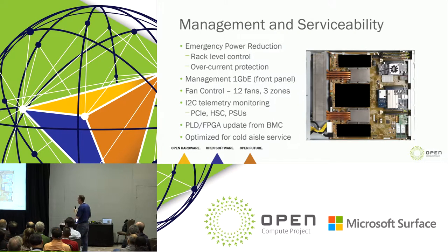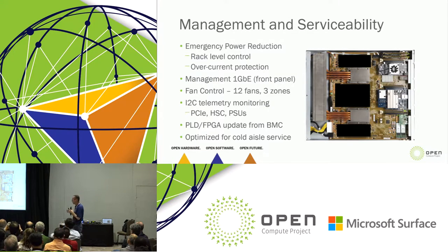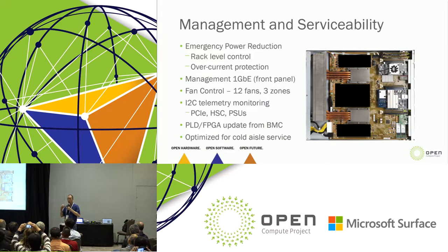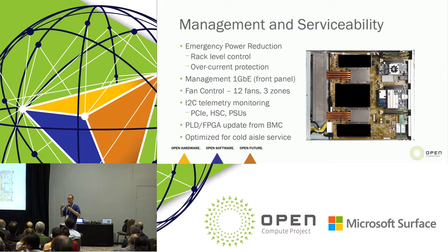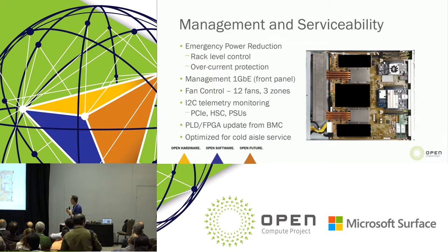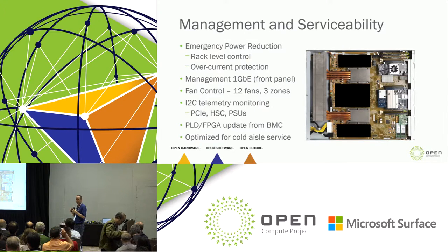When we look at just the motherboard itself, our partners really care about emergency power reduction. We do that at the rack level — detecting the power of the rack and throttling at certain key set points. That enabled us to load more servers into the rack and not over-provision, getting closer to the rack's power limits. Internally on the board there's going to be over-current protection so that the system can go down gracefully in the event of something catastrophic.